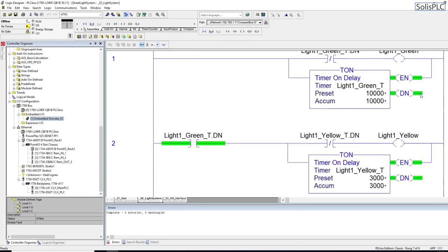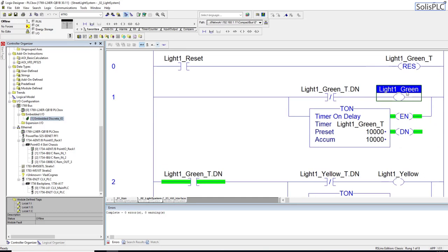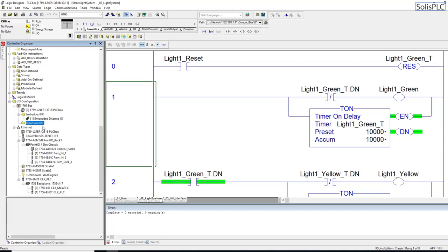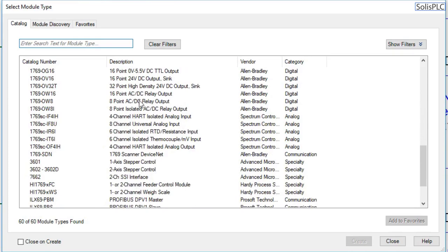Also, what I've mentioned before is that in a system, doesn't matter if it's a street light or it's perhaps some kind of a tank filling system or a valve system, you always have some kind of a feedback. So when you try to open a certain valve, you want the feedback that the valve has been opened. And a system that doesn't have feedback is, it's not uncommon, but it's essentially a lot more prone to errors. So we're also going to be looking for an input feedback. And in case of lights, they can either be on or off. So it's essentially going to be one single feedback back from the light. When we tell it to come on, has it actually been turned on? So that should tell us that it's going to be a digital signal back to the PLC. Now, of course, when you go into this expansion IO and you want to add a new module, you will notice that you have a lot of different options.